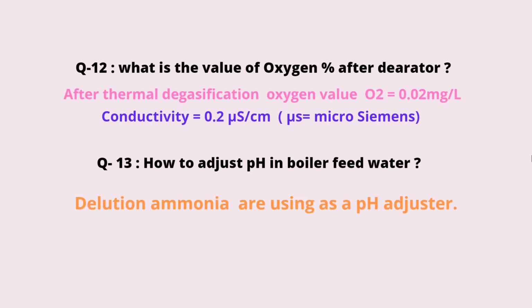What is the value of oxygen after the deaerator? After thermal degasification, the oxygen value is around 0.02 mg per liter. Conductivity is 0.2 microsiemens per centimeter. How to adjust pH in boiler feed water? Diluted ammonia is used as a pH adjuster.